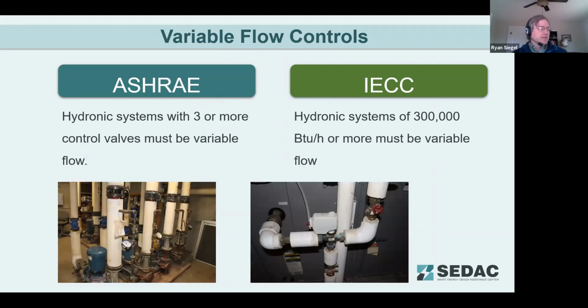Well, variable flow controls, again, this is a little bit different. ASHRAE says if you've got at least 3 control valves, then you need to have variable flow. Whereas IECC bases it on the size of the system. So if your hydronic system is over 300,000 BTUs, then you have to do variable flow.